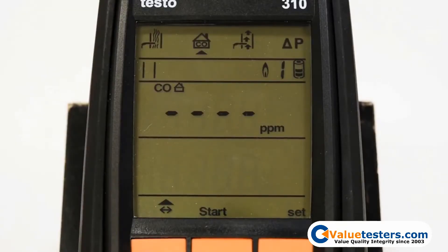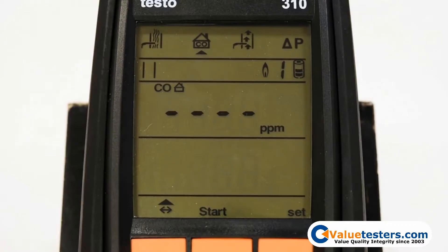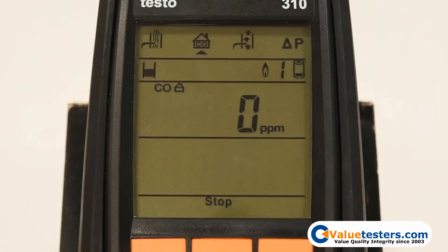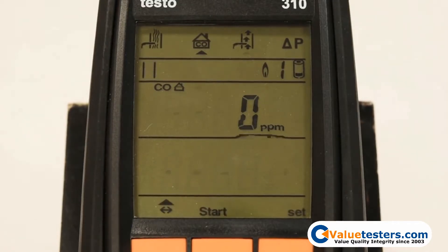Selecting the Ambient CO measurement will set up your analyzer to measure CO in spaces around a home. Pressing the center orange button will start and stop this measurement. It is important to note that cigarette smoke will influence the measurement value by more than 50 parts per million.